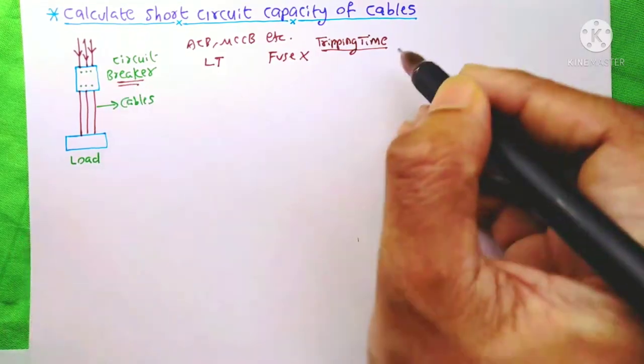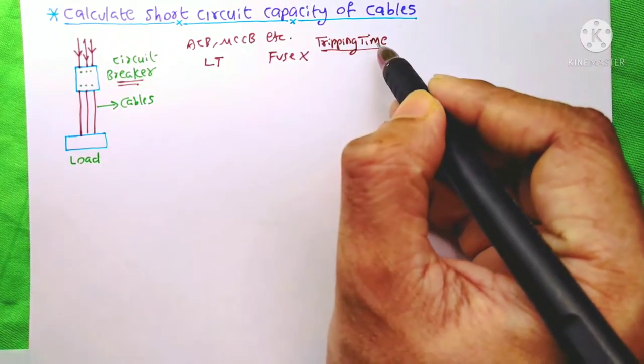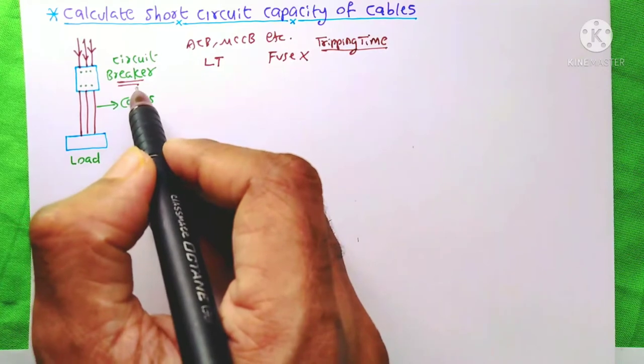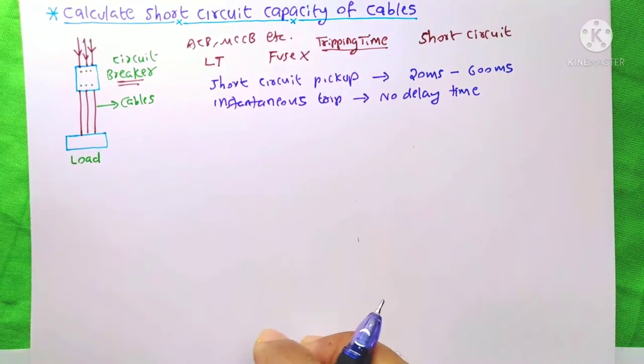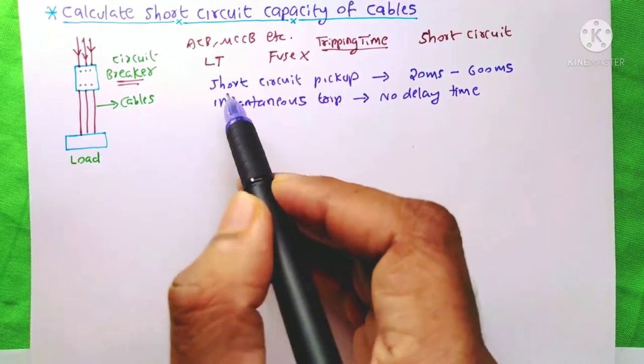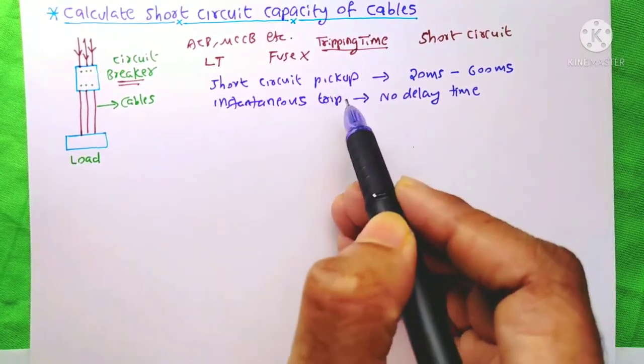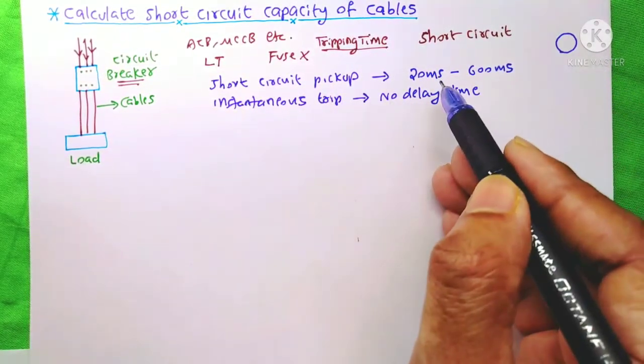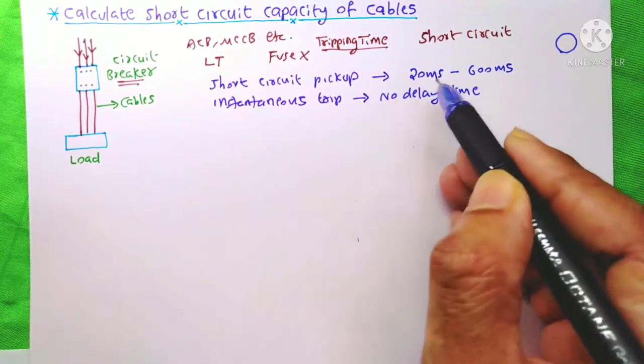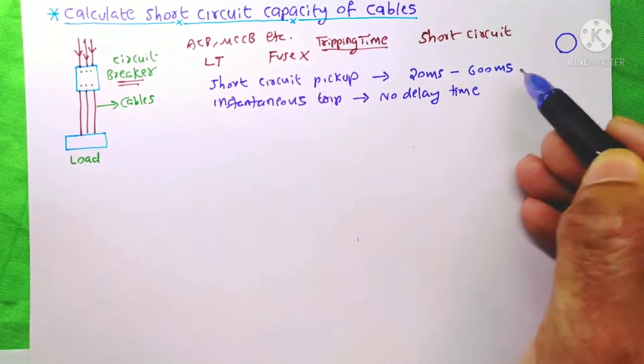Because for this calculation, short circuit tripping time of the circuit breaker is needed. On air circuit breakers and also in MCCBs, we can see the short circuit pickup setting. The tripping time is generally between 20 ms and 600 ms.